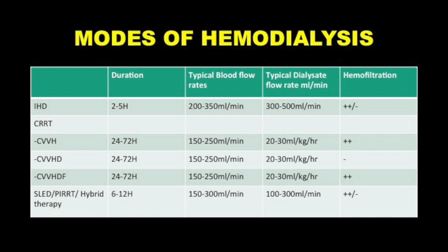What this tries to do is adapt equipment normally used for regular intermittent hemodialysis for sicker patients by lowering the blood flow and the dialysate flow. We still have trouble though. The most common machines here aren't able to play the games we want to play with the dialysate flow range. Most of our dialysis machines will stop at 300 ml per minute; they won't drop as low as 100 ml. I don't know if other equipment is able to drop that low, but all of our equipment in Mulago cannot drop, so we really cannot vary our SLED prescription as much as we would like.